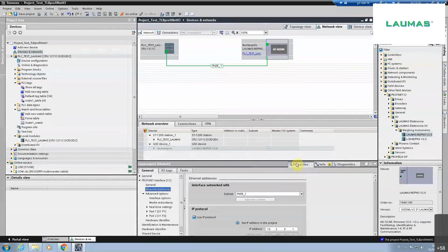Now, selecting the device and accessing the Properties section, we are able to define two very important parameters for the correct functioning of our Profinet network. More in detail, we can set the IP address that will be assigned by the PLC to our TLB instrument during the network initialization, and we can set the device name. Device name is fundamental during the initialization of the network and during the management of the devices by the PLC.